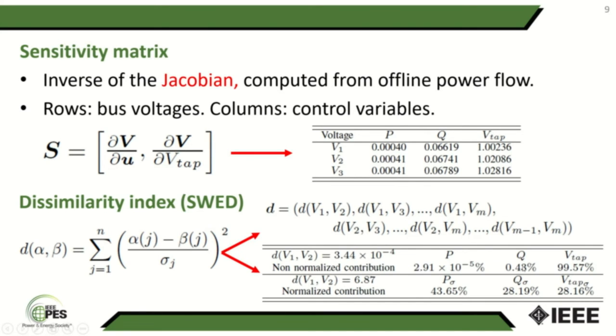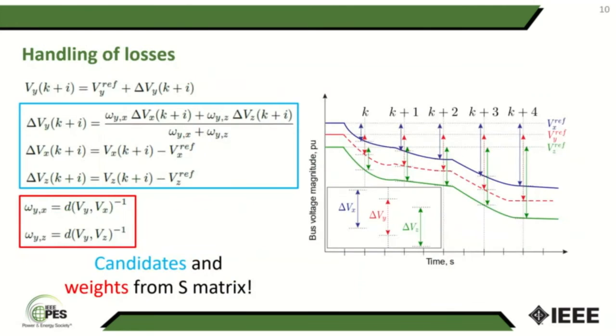We can see how the upper line is not normalized and how the lower one is normalized. On the first one, the tap of the transformer will dominate over the rest of the variables, and on the second one, this effect is more distributed. The best two candidates will be the most similar to the lost measurement bus. In essence, the two with the lowest dissimilarity. The weights to build the pseudo measurements are based on the inverse of the dissimilarity. This means all of the required information comes from the sensitivity matrix.